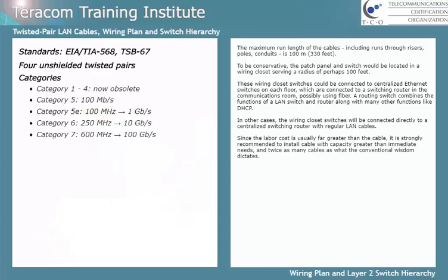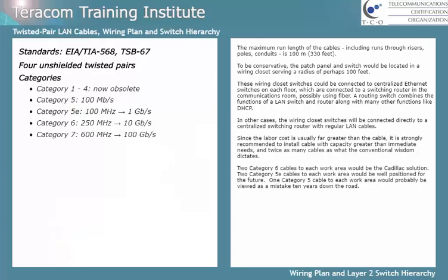Since the labor cost is usually far greater than the cable cost, it's strongly recommended to install cable with capacity greater than immediate needs and twice as many cables as conventional wisdom dictates. Two Category 6 cables to each work area would be the ideal solution. Two Category 5e cables to each work area would be well positioned for the future. One Category 5 cable to each work area would probably be viewed as a mistake 10 years down the road.